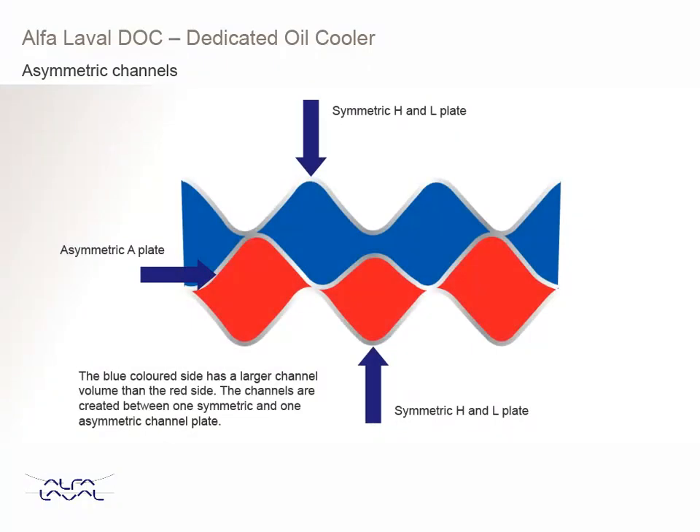For some of the Alfa Laval DOC models, we have asymmetric channels. Asymmetric channels provide better utilisation of the allowed pressure drop on both sides. This means that the channel volumes are different for the cold and hot sides. With this, you can optimise the heat transfer and thereby minimise the number of channel plates in the unit. Asymmetric plates are normally combined with a symmetric H or L plate.